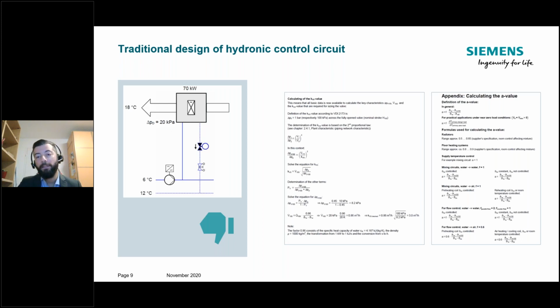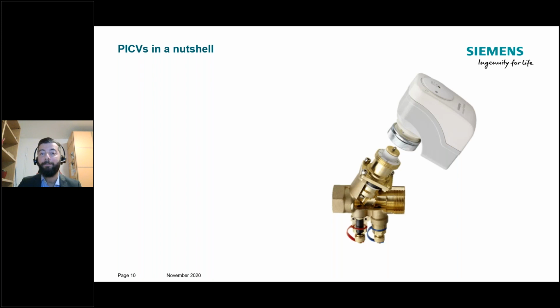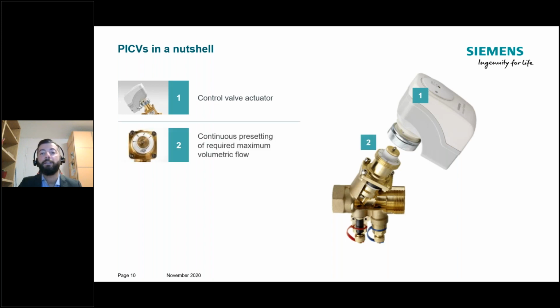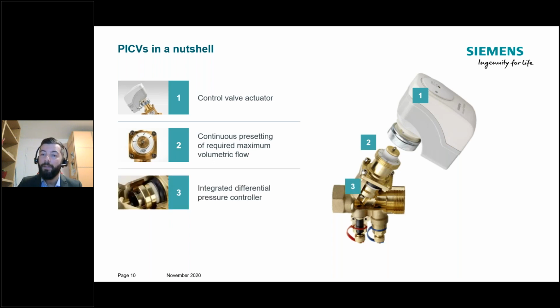But if you want to optimize the efficiency of this process, then you can opt for PICV. But what is a PICV and why are the benefits not only related to the commissioning and water balancing aspect of the whole project? Let's see, it's just a recap. A PICV is typically 3 devices in one. It's a control valve with an actuator on it. It has a manual flow presetting, and the dynamic balancing is granted thanks to a mechanical differential pressure regulator built in the valve.